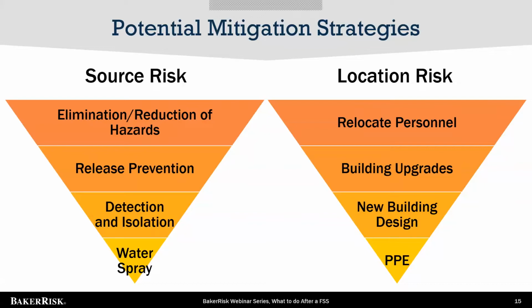For strategies that could mitigate a potential release from an external impact, consideration should be given to installing physical barriers, such as crash bollards, preventing personnel from lifting over operating equipment, increasing the depth of cover and visible signage for pipelines, for example. For releases due to internal or external corrosion, you could use an exotic metal material, have double-walled piping, or increased inspection.